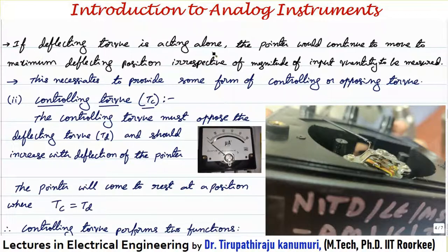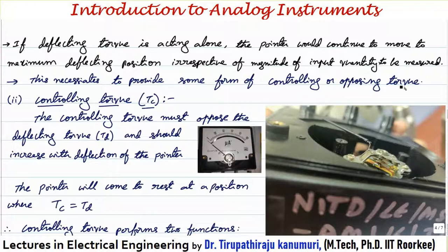If deflecting torque acts alone, the pointer will continue to move to the maximum deflection position irrespective of the magnitude of the input quantity. This necessitates providing a controlling or opposing torque. For example, in a PMMC instrument, when current passes through the coil a torque is produced pushing the pointer — without opposition, it would go directly to the final maximum position regardless of current magnitude. So a controlling torque, such as from a helical spring, is provided to oppose the movement.